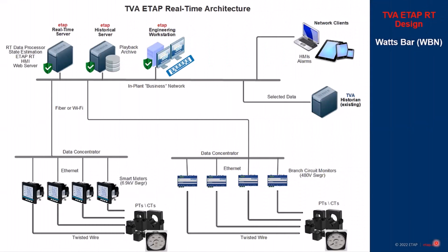This shows the overall architecture of one of our ETAP real-time systems, and you can see we've got smart meters and branch circuit monitors down below. The idea is that we would install a data concentrator somewhere near our 6.9 kV switchgear rooms, and another data concentrator somewhere near our 480 volt switchgear rooms. And these branch circuit monitors and smart meters would be connected via Ethernet to the data concentrator. And then we'll go either over fiber or Wi-Fi back to the ETAP real-time server, which is located near the plant control room.